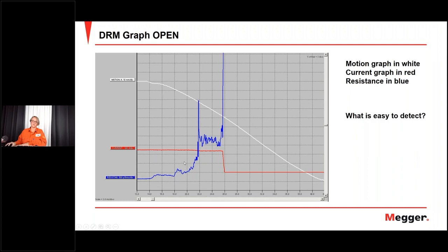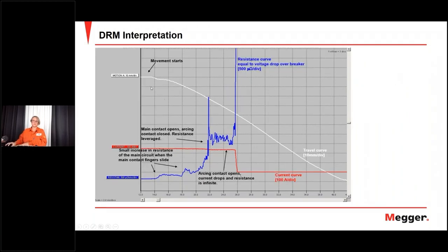So in here, you have the arcing contact and the main contact in parallel, while here only the arcing contact is in the circuit. So you have movement start, you have a travel curve, you have a resistance changing, going up to a step, and then total release. So the current will go to zero. So what you want to look at is mainly the distance between this and this, and that you can read out from this motion graph, because this is here in the same time and graph.